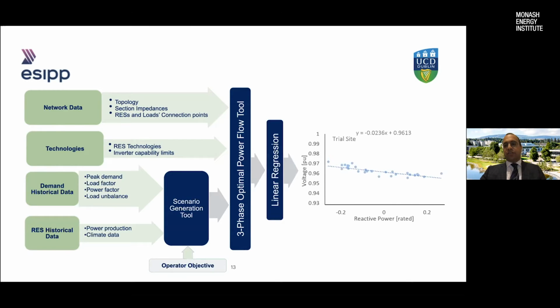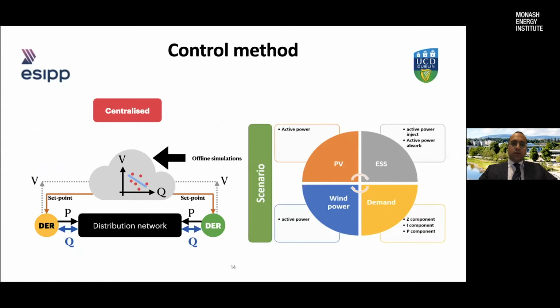And then, using linear regression, we found the graph that works for us. When we talk about the volt-var curve, in a very simplistic form we are talking about a straight line. It can actually be a curve, but in a simple form it can be linear. We found the slope of this line, and the equation describing it is obtained based on some objective function. So when each unit is connected to the grid, it senses the voltage at the connection point and then understands how much reactive power should be injected into the grid. There are two ways of doing that. Once you obtain the volt-var curves for each individual DER, you can send signals from a central unit to each one and tell everybody what to do.